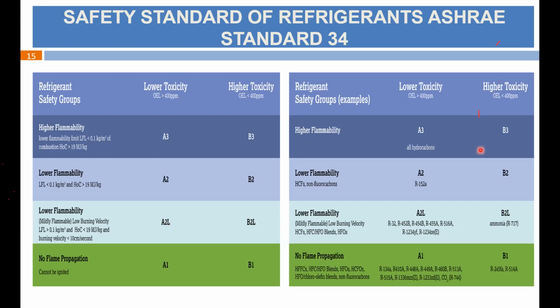Now see this refrigerant safety group. All these hydrocarbons are lower toxicity but highly flammable, so they mainly come under the A3 category. Another refrigerant with lower flammability is R152A, that is difluoroethane, C2H4F2. This refrigerant is mainly used for automobile air conditioning. So this is lower toxicity but lower flammability. And in the A2L category, as you see, there is R32, which is very much used nowadays, especially in the room air conditioner.